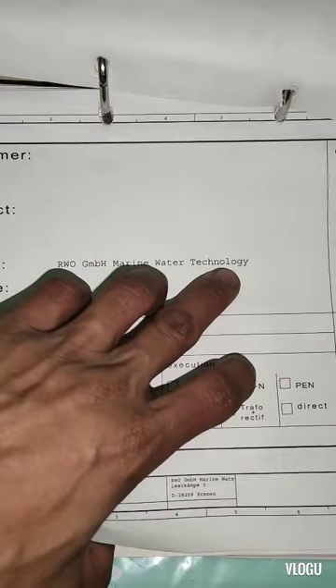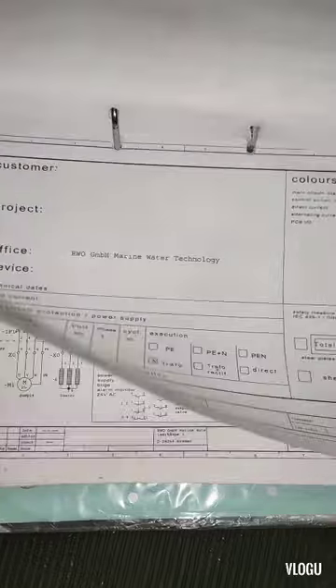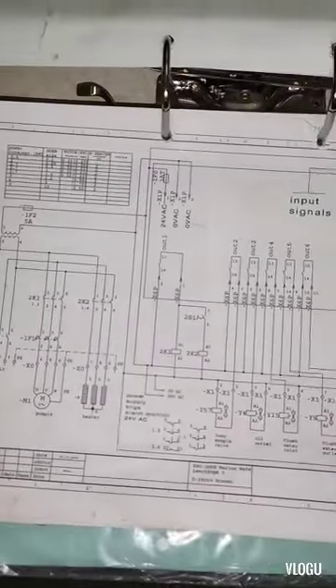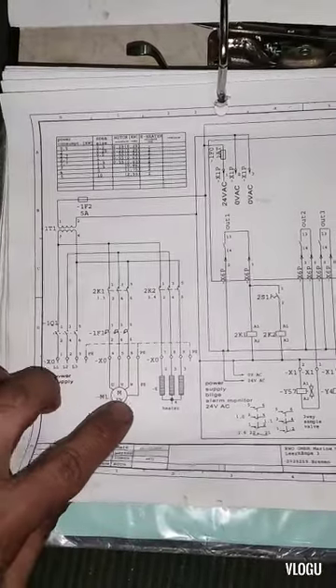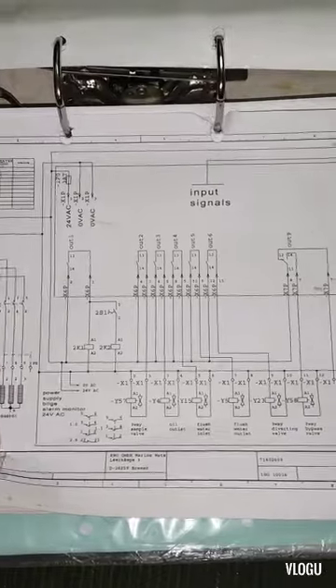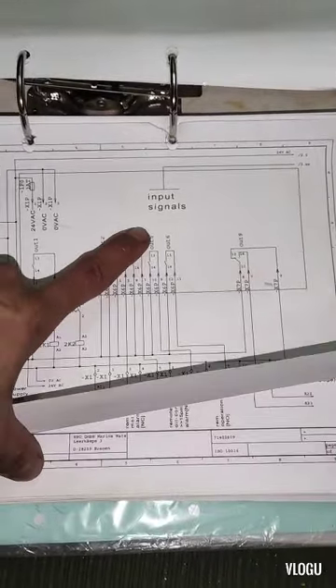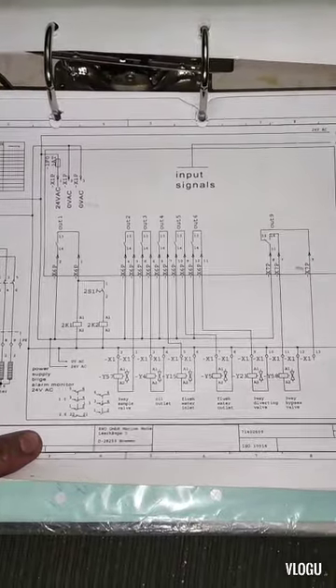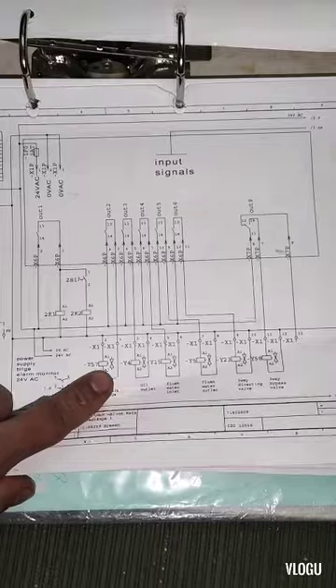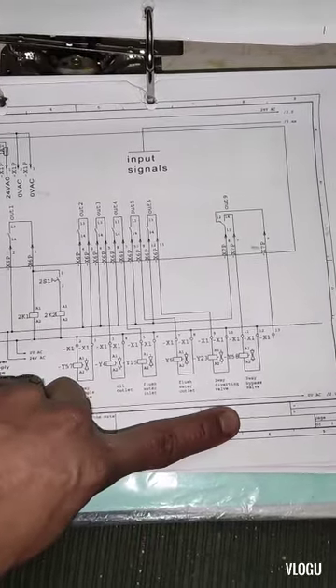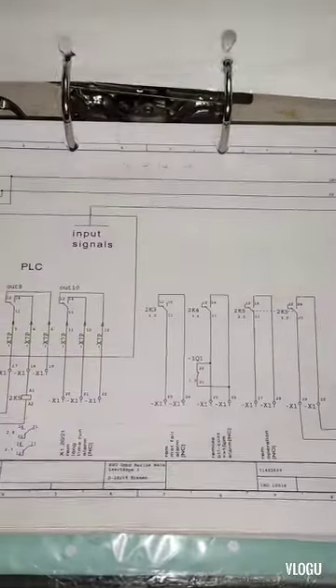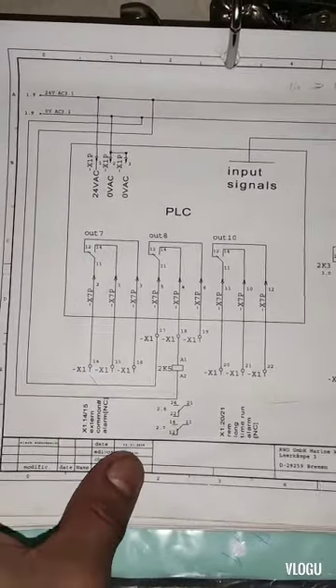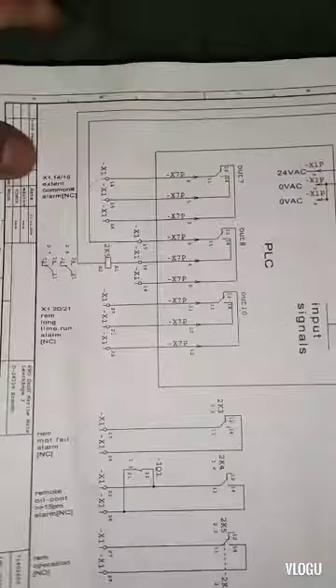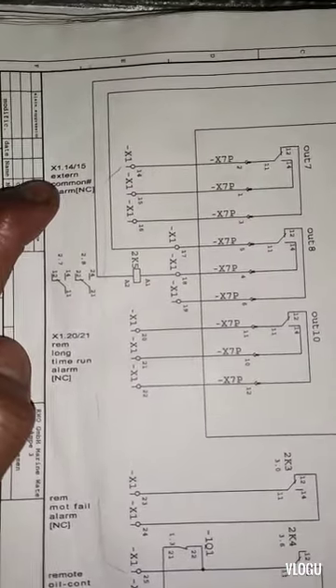What I'm trying to find out in the manual is the signal that gives the alarm on the engine control room. Here is the drawing. Motor pump, heater. You have input signals for the PLC. And then control valves, solenoid valve. We have the PLC input signal here. And we have here the external common alarm here.